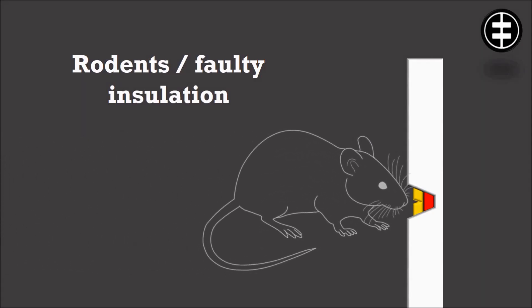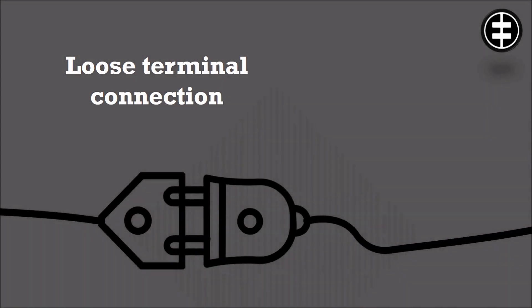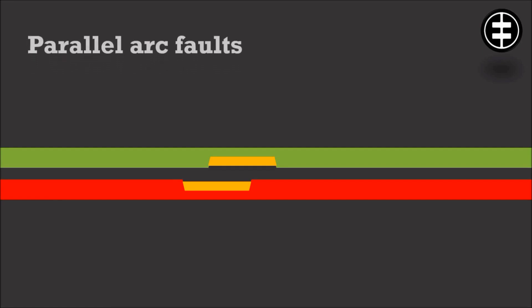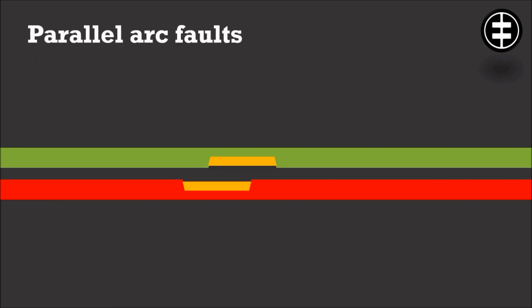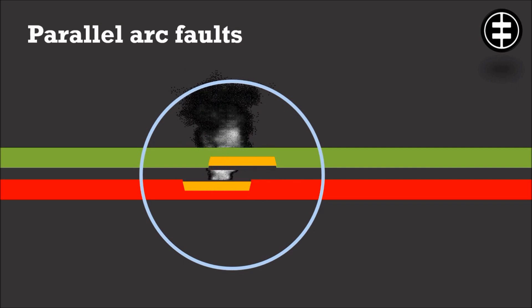Rodents, faulty insulation, and loose terminal connections are all factors which could lead to one of three different types of electrical arc faults. Series arc faults is the first type — these occur between two parts of the same damaged conductor. Parallel arc faults is the second type — these happen between two different conductors with different voltage levels when the insulation is damaged.